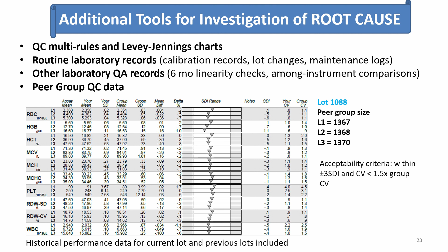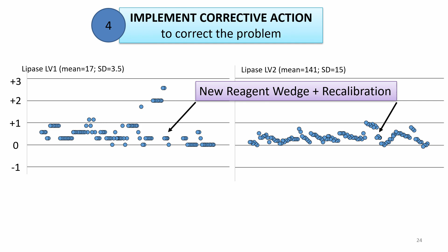So once we've identified the root cause, we now want to implement corrective action to correct the problem. Here I've shown that. For this lipase problem, we have put on a new reagent wedge. When we put on a new reagent wedge for this assay, the manufacturer recommends recalibration, so that's what we did. And you can see that QC came back into the acceptable range. So most of the time we would say, great, we fixed the problem, we can recommence patient testing, which is true. But this is not the end of the recovery process.